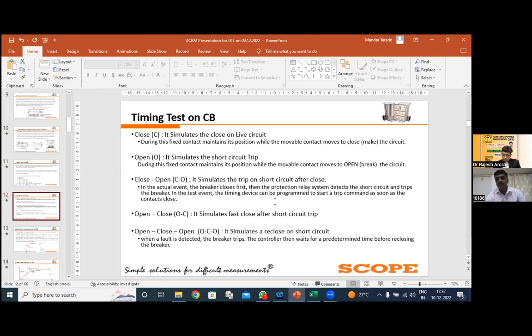The next test is the OC test, that is the open-close test. It is basically used to simulate the fast close after short circuit trip. Many people are not performing the OC test at the time of doing the health assessment or the diagnostic test of the CB. Then the OCO test is basically to check whether your auto reclosure mechanism is working satisfactorily or not. Apart from that, there is one more test, called the PDR test, where we are checking whether the PDR, pole discrepancy relay, is operating satisfactorily or not. So these are some of the tests which we are performing as a timing test on the CB.